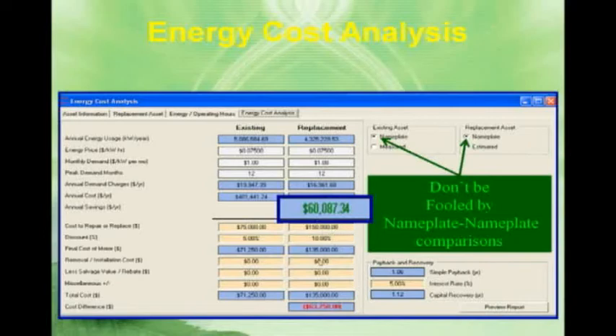However, when you go down through, looking at just simply nameplate of the new motor versus nameplate of the old motor, and you look at the power used and the energy saved, okay, at the bottom it ends up being a $63,000 investment, but with the annual savings of $60,000 a year, okay, over here on the bottom right-hand side, you can see that that's about a 1-year payback. Well, now, if you go to the accountant with that, a 1-year payback's pretty easily authorized.